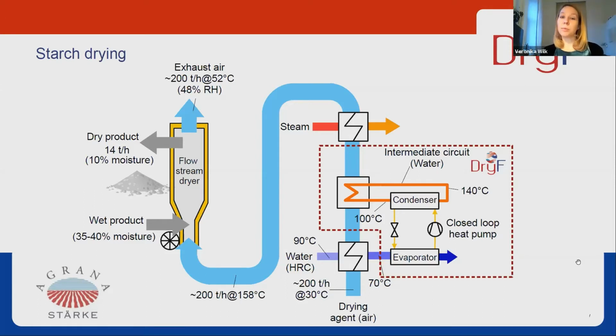And the heat pump demonstrator has a lower heating capacity than is needed to fully supply that drying process. So we have heating capacities of around about 400 kilowatt, and the whole system requires 4 megawatt of heat. So it's 10%, which is a good size for a research and demonstration object to learn from the real behavior, but not being excessive on costs and investment. So that's for the starch dryer.